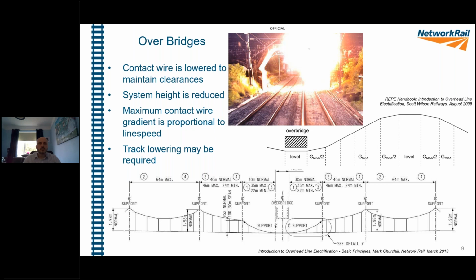In many circumstances, on our Victorian railway system, we don't have these clearances. In these cases, we have to register. So registration is where we hold the contact wire to limit it in a horizontal plane. And so the contact wire is registered underneath the bridge itself. We use special registration arms called underbridge arms in these circumstances. And these limit the amount of uplift of the overhead line equipment to maintain the clearance between the bridge and the contact wire. The first thing we need to do when electrifying a low overbridge is to think about how we're going to fit the wires through.